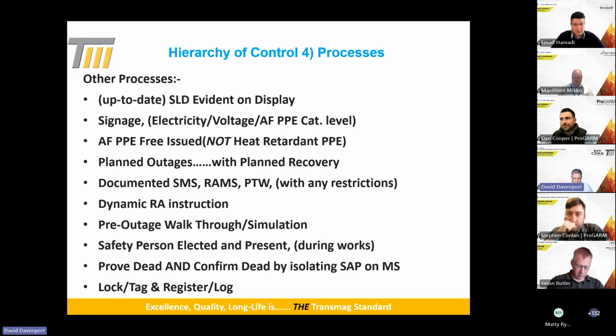With every work that involves electrical isolation, there should be a safety person elected and present during that work. And obviously the prove dead and confirm dead, but the lock, tag, and register log - I come across a lot of companies that use lock and tag or LOTO, but they don't have a process in place. They don't have a register, they don't have nominated signage and things like that.